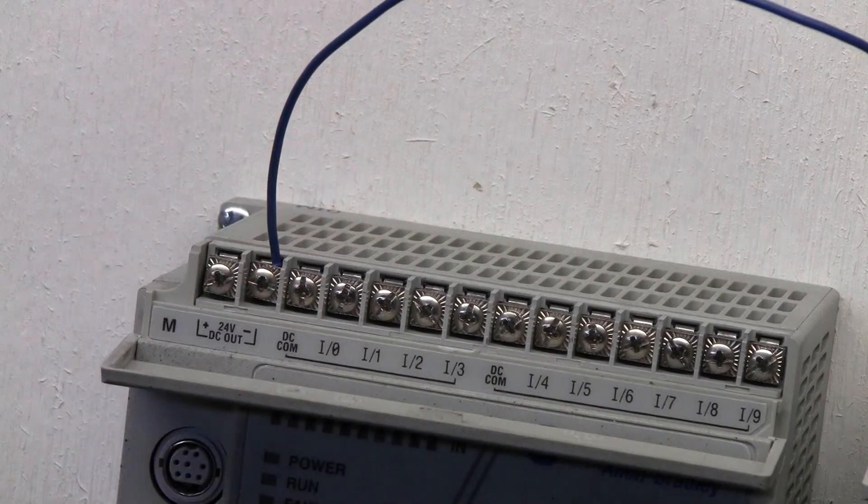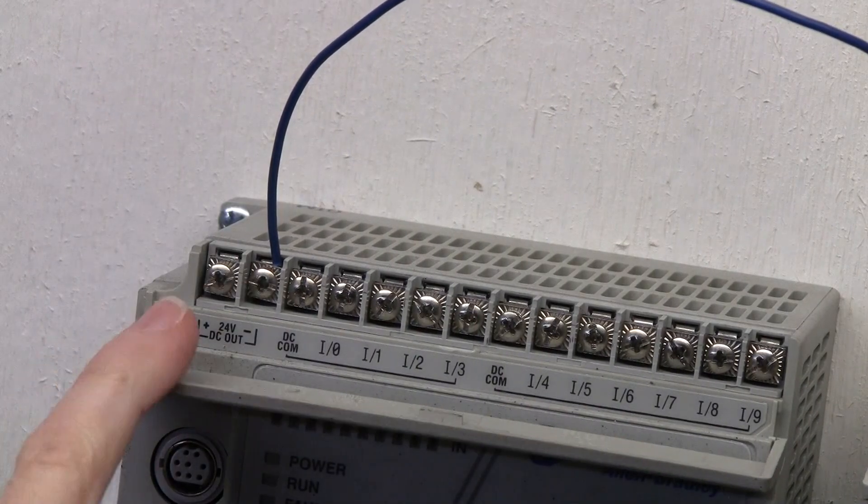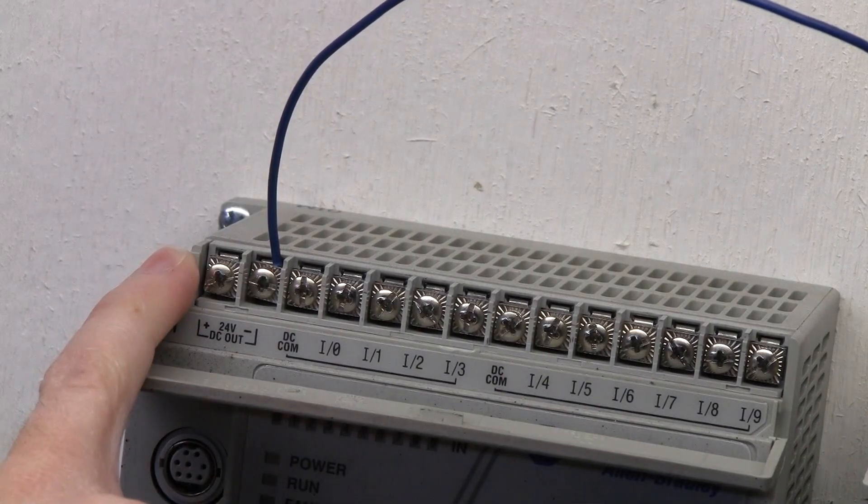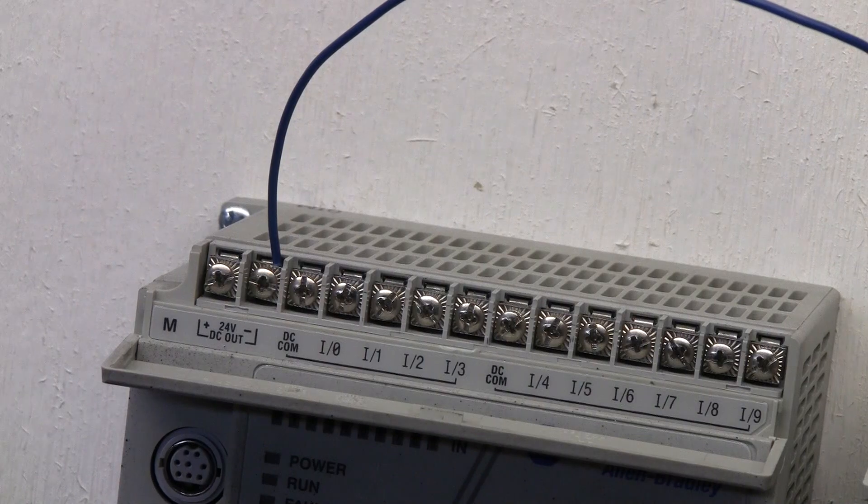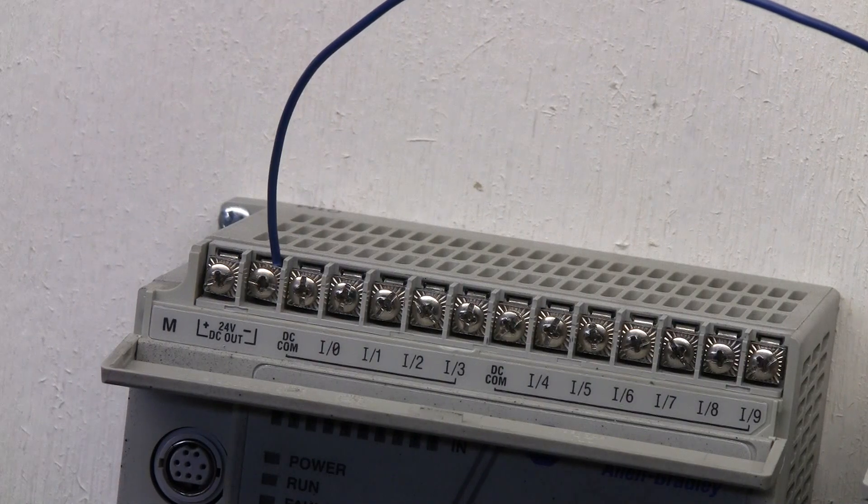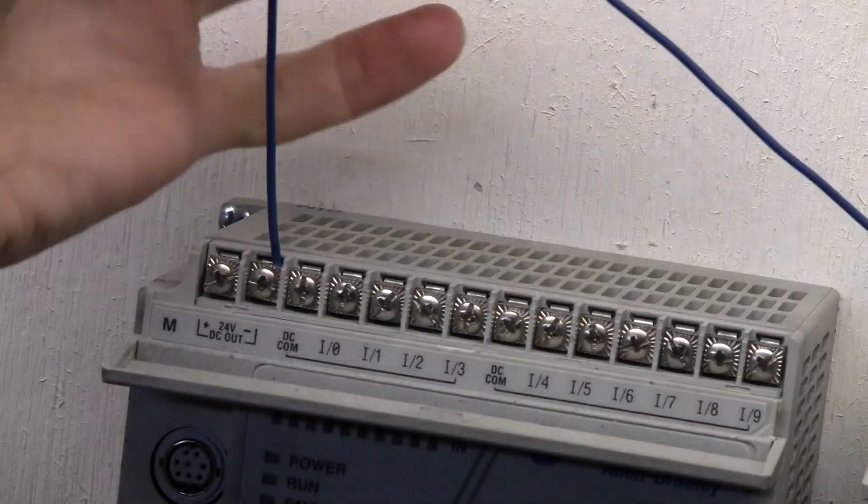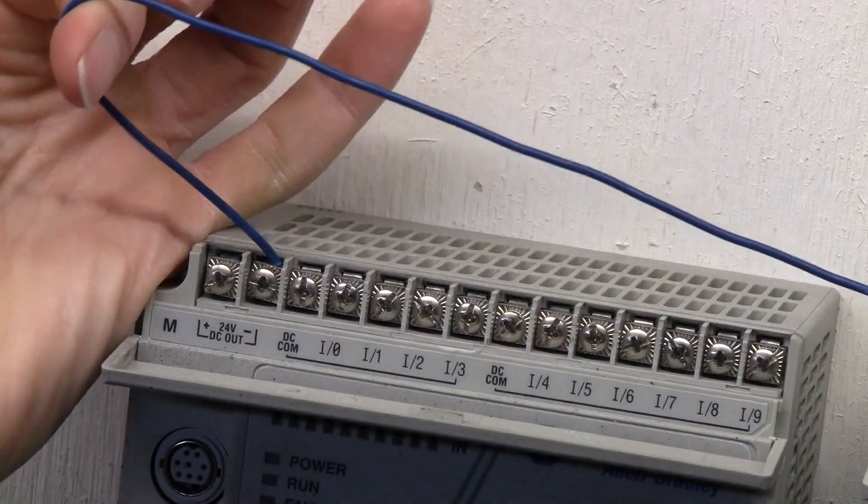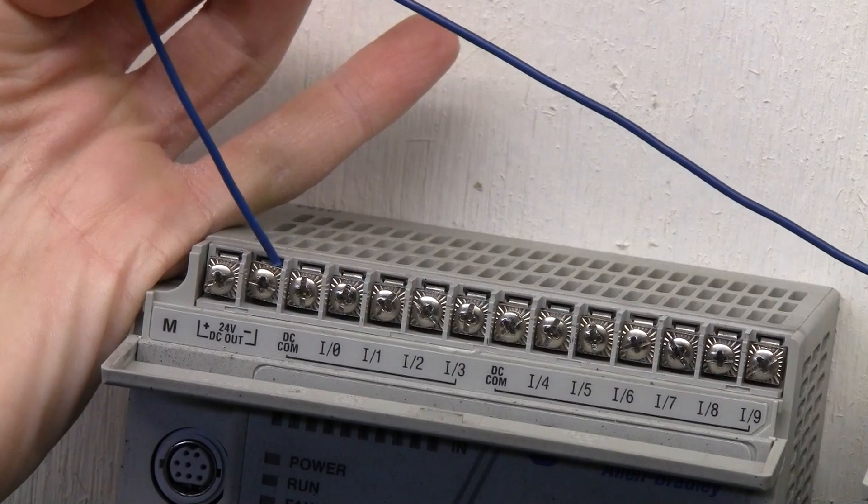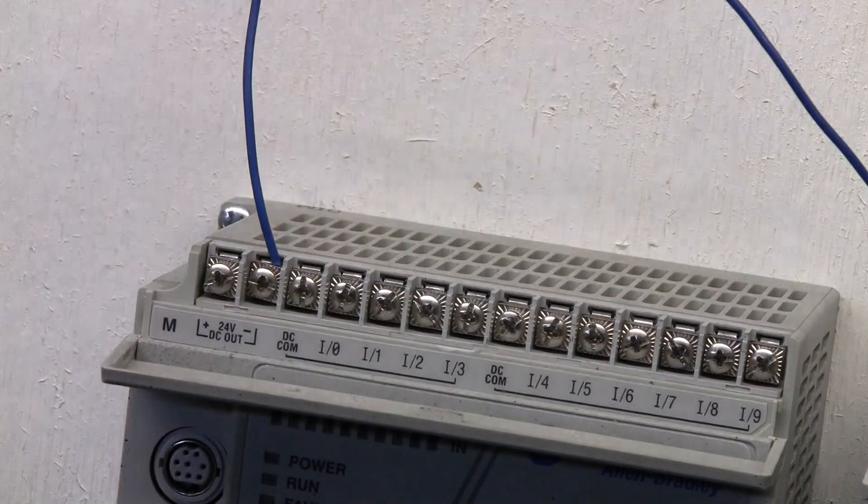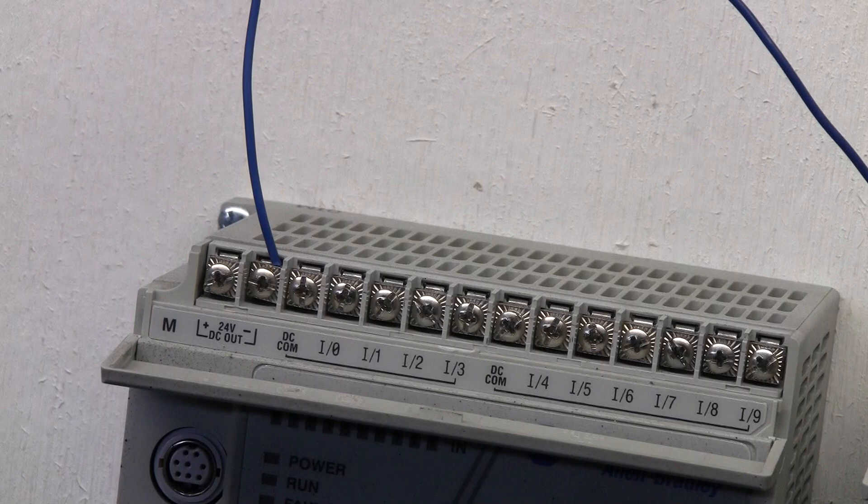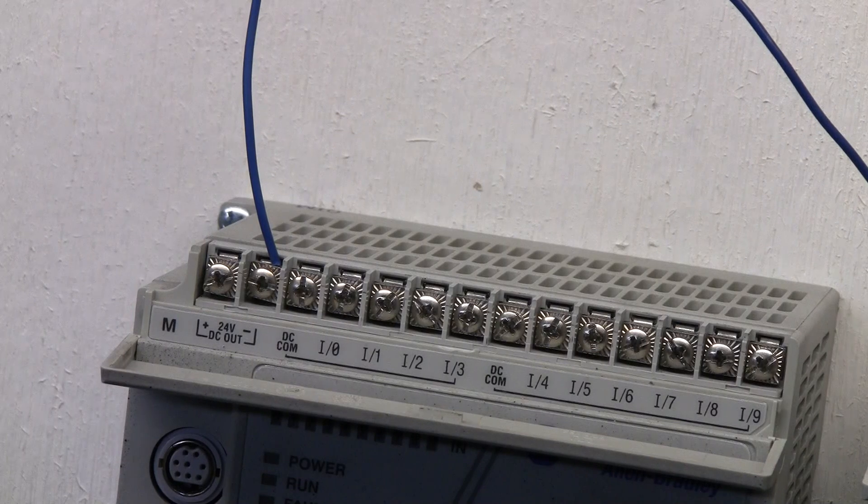Now that those are connected, it won't matter where we draw the positive from. We can draw the positive from this particular terminal or go back to the other PLC. Either way, we'll always have a combined or joined DC bus together. Wherever we choose to take it from, we have a combined DC bus.